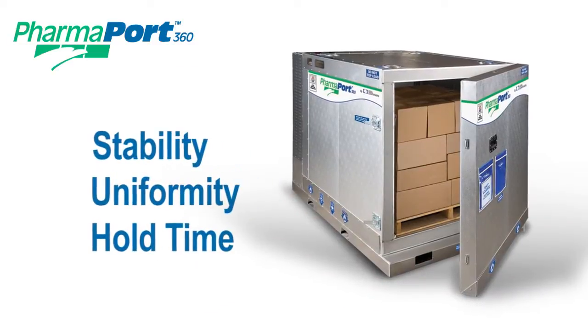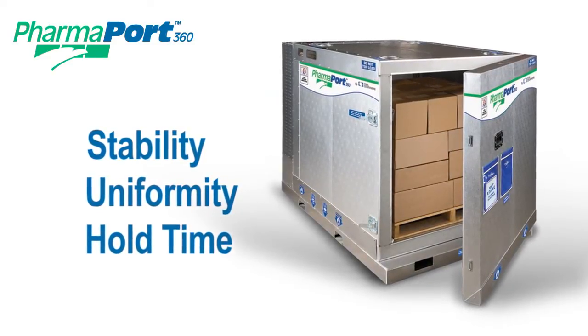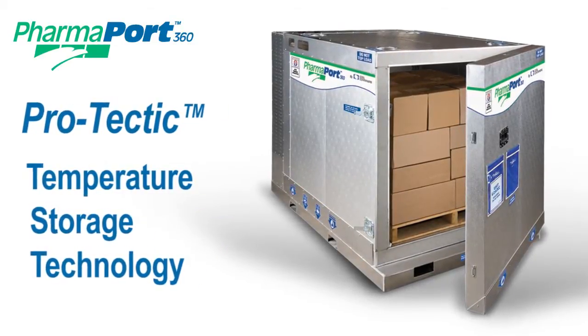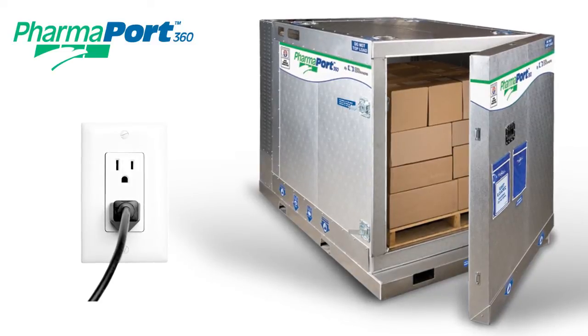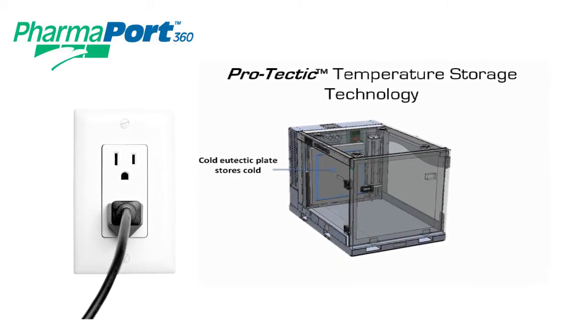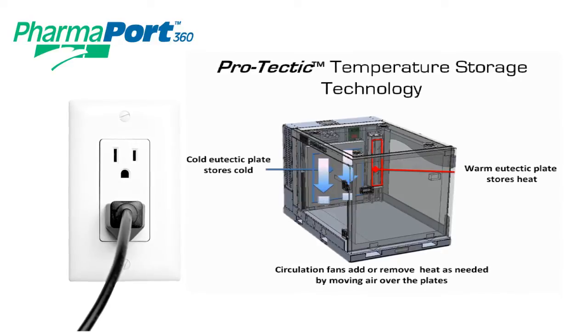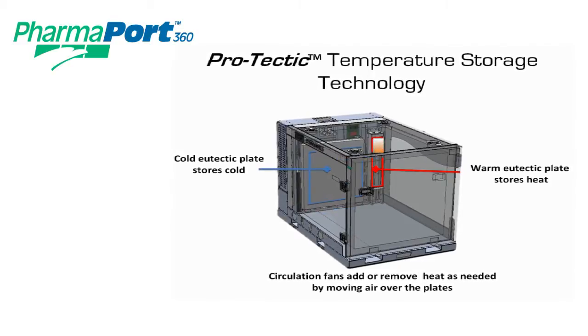The PharmaPort's exceptional temperature stability, uniformity, and hold time is achieved with the use of state-of-the-art vacuum panel insulation combined with Cool Container's exclusive Pro-Tectic temperature storage technology. The PharmaPort simply needs to be charged by plugging it into any electrical outlet, and with the included plug adapters, the PharmaPort can be charged anywhere in the world. When plugged in, onboard refrigeration and heating systems are used to store cold and heat in internal eutectic phase change plates. The onboard battery is also charged. When unplugged and in transport mode, circulation fans move air over these storage plates to lower or raise the temperature as needed to precisely maintain the condition of the cargo.